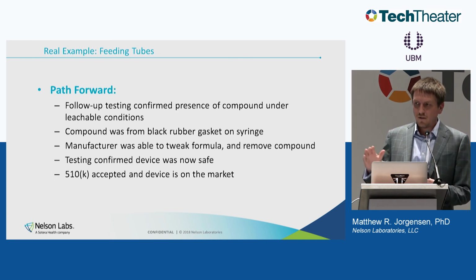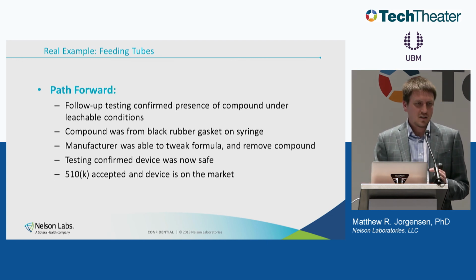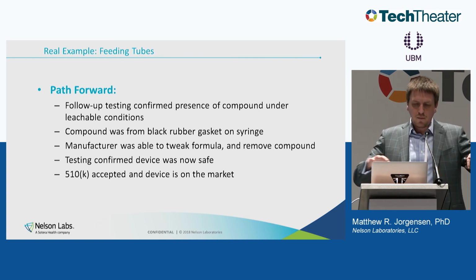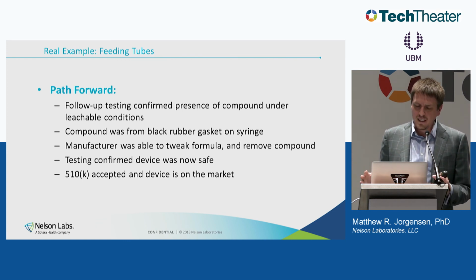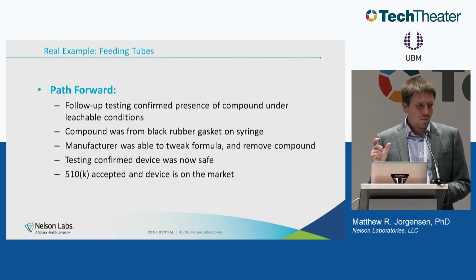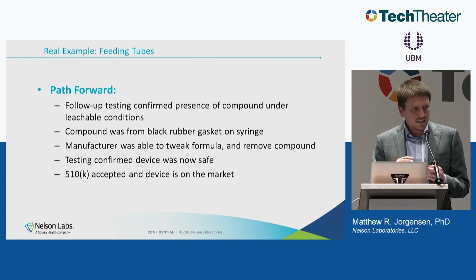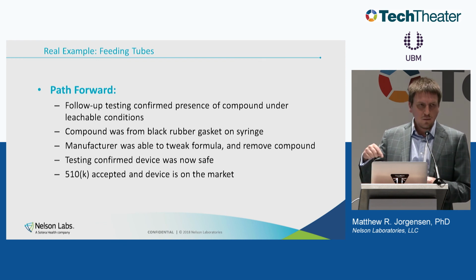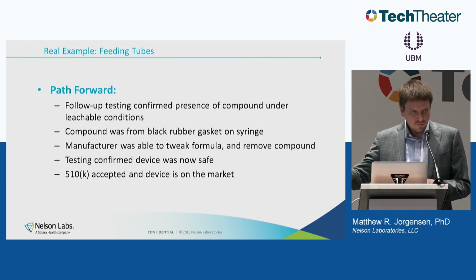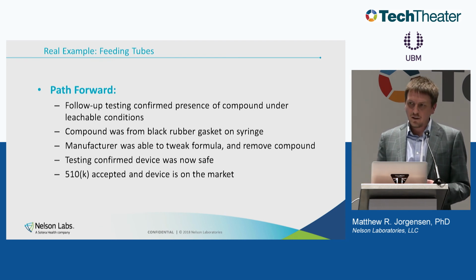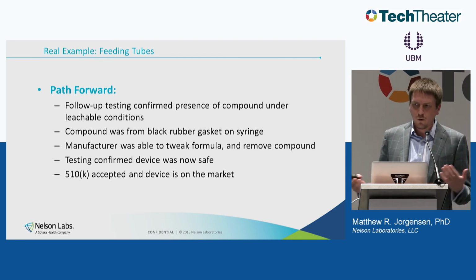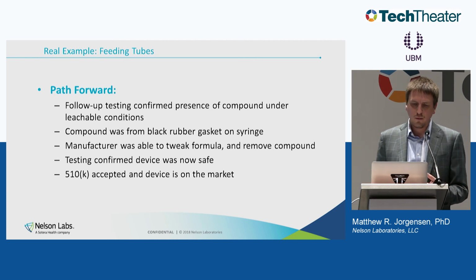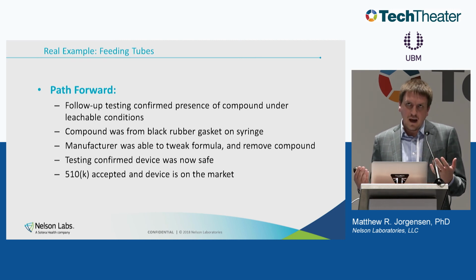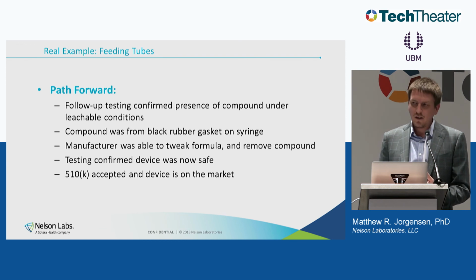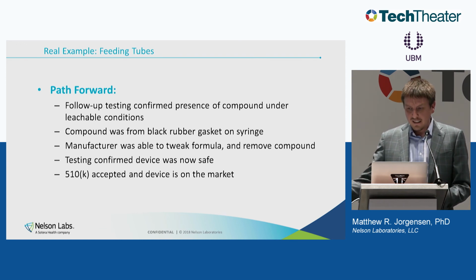So the path forward there was, since we had identified what this compound was and we had broken up the parts of this kit into different pieces, we knew that it came from the black rubber syringe gasket in the syringe to deliver the food. So the manufacturer was able to go back to the maker of the black rubber syringe gasket, and the manufacturer was like, oh yes, of course, we know this compound, it's a vulcanization agent, we use it to make the rubber more stiff, and yeah, we have alternatives for that, we can reduce the amount. The manufacturer of the gasket made that change.